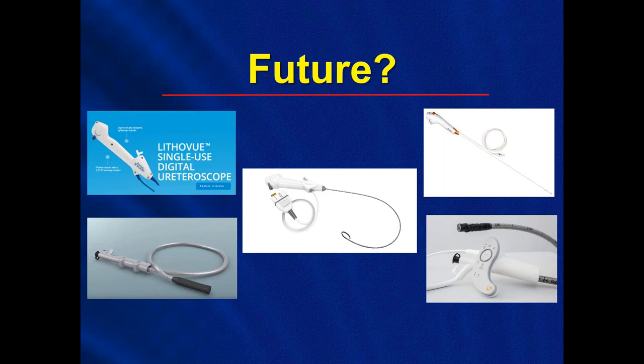I will share that as a result of infection concerns, cross-contamination, and the inability to really guarantee that our scopes were being cleaned and handled properly, my OR has literally stopped reprocessing reusable scopes and only uses single-use flexible cystoscopes, ureteroscopes, bronchoscopes, and rhinoscopes, as well as intubation scopes. Our GI department, which is extremely busy, is still fully involved in the reprocessing of reusable scopes. But for these other scopes in the OR, we've actually gone to single-use across the board, which reduces our risk for lawsuits and for cross-contamination. The hospital really took that into consideration when they made that decision.